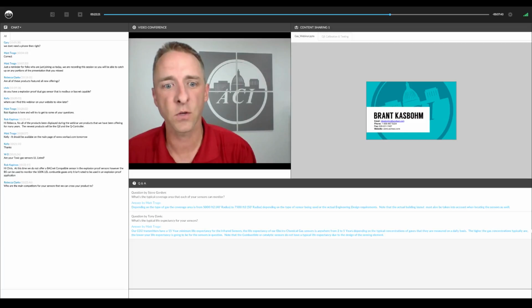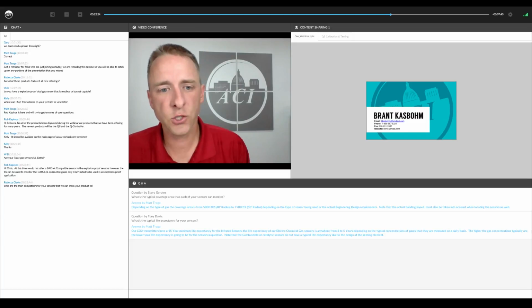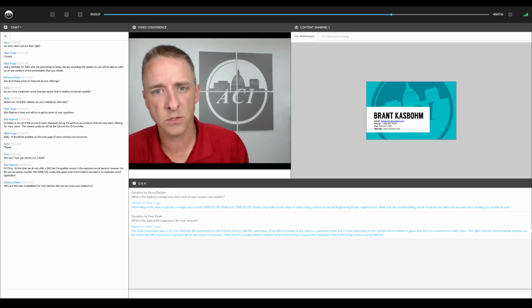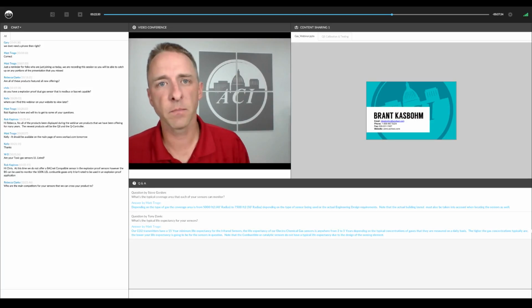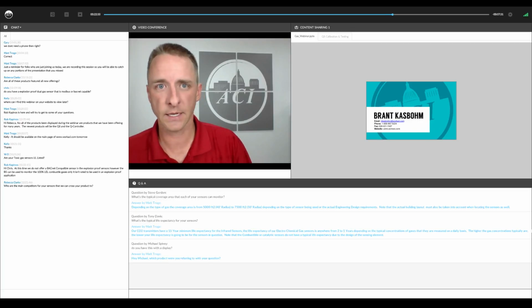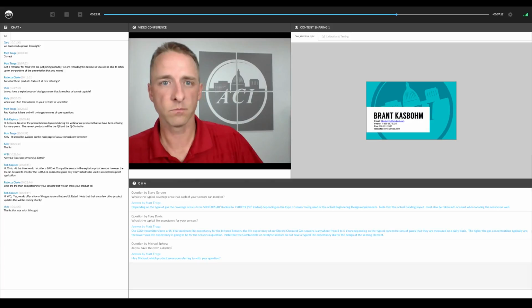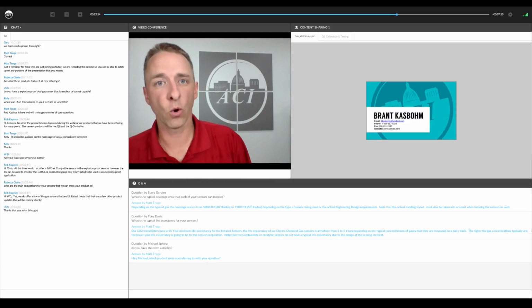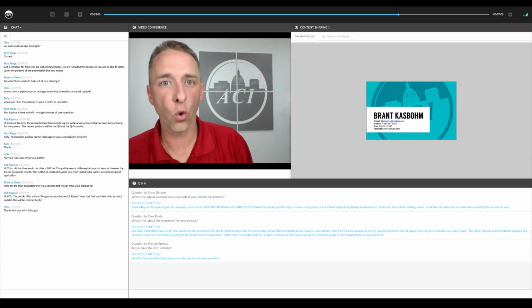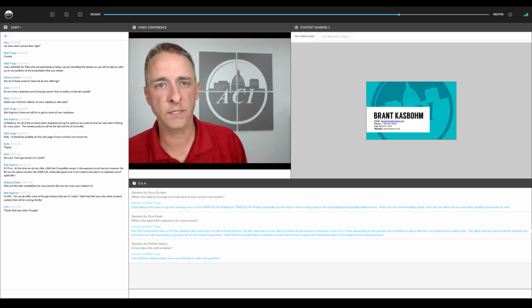Next question is, how high should we be mounting the gas transmitters? Good question. We do have a recommended mounting height, and that's going to vary based on the specific gas that's being measured. And we base our recommended mounting height on the actual chemical weight of the gas. So, for example, CO gas is the same weight as ambient air. We would recommend that sensor be mounted 4 to 6 feet off of the floor, where head height is. For example, NO2 gas is heavier than ambient air, so we recommend that sensor be mounted at the floor or as low to the floor as possible, because over time that gas will sink to the floor, and that's typically where people are working as well.